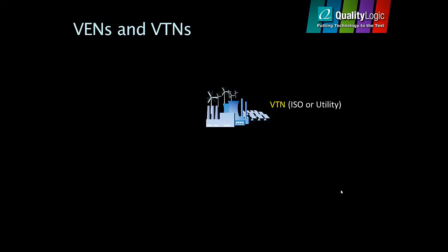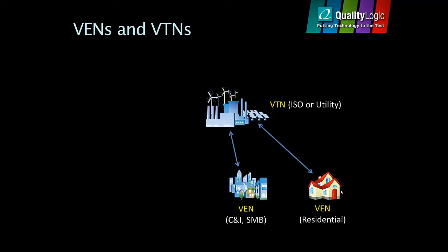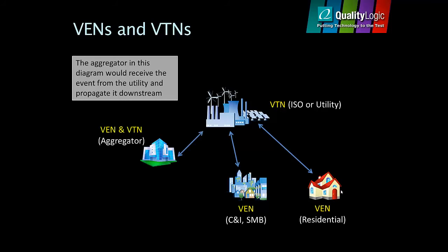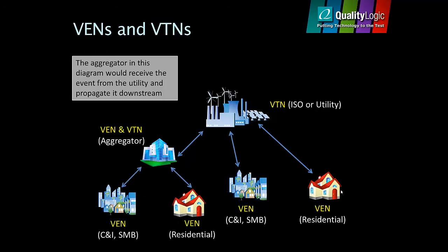A typical interaction pattern would have the utility playing the role of VTN, communicating with a residence or small business playing the role of VENs. Or, perhaps the utility playing the role of VTN would first communicate with an aggregator, playing the role of a VEN, who would switch hats, becoming a VTN, in order to propagate events downstream to other commercial or residential resources playing the role of VENs.